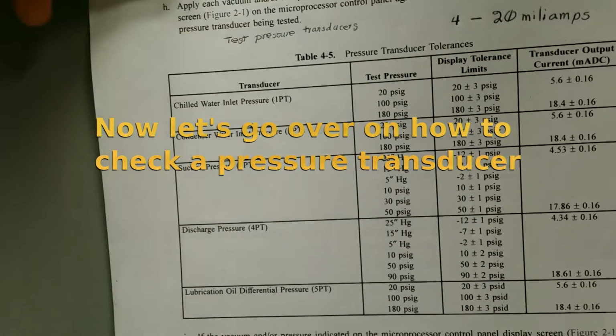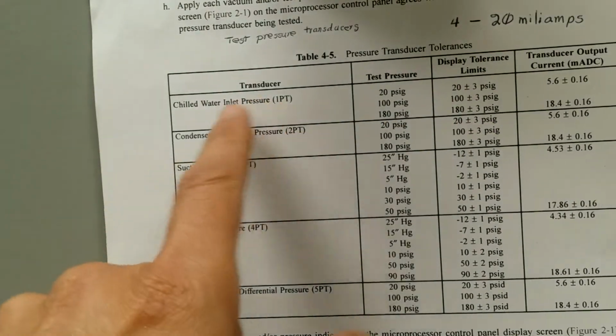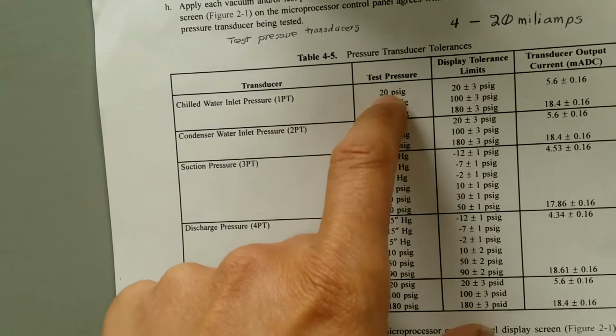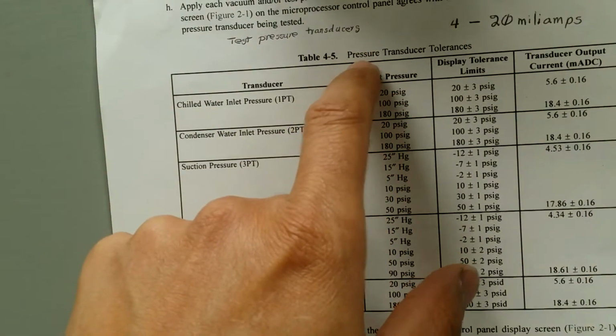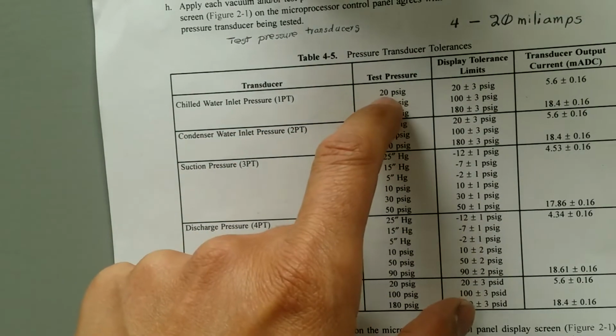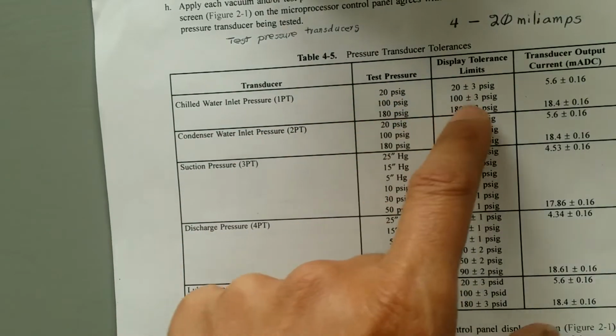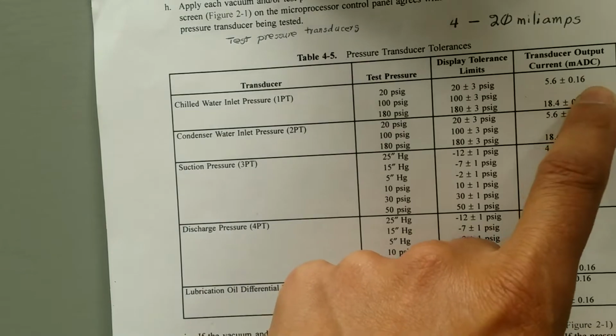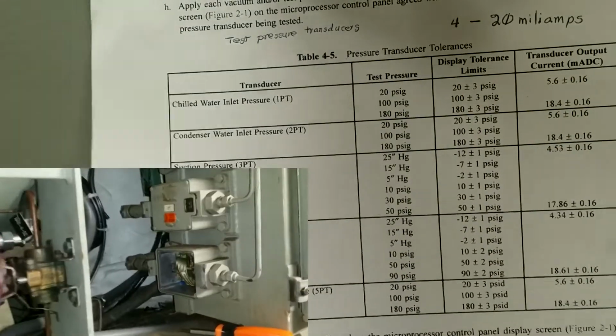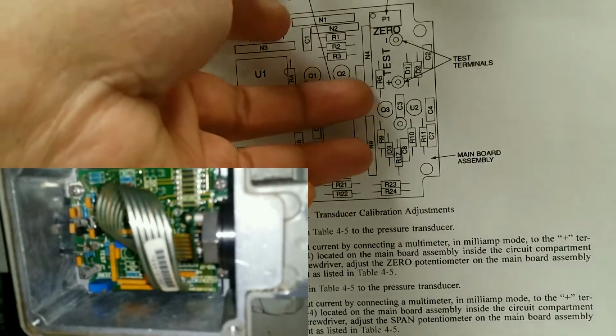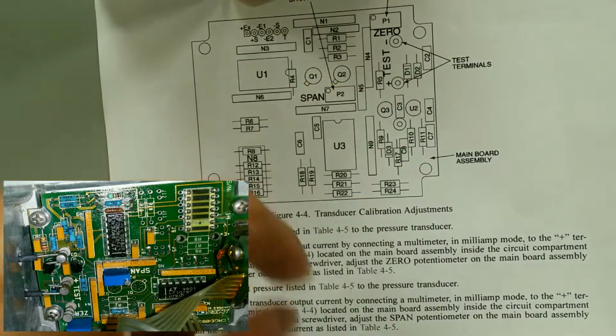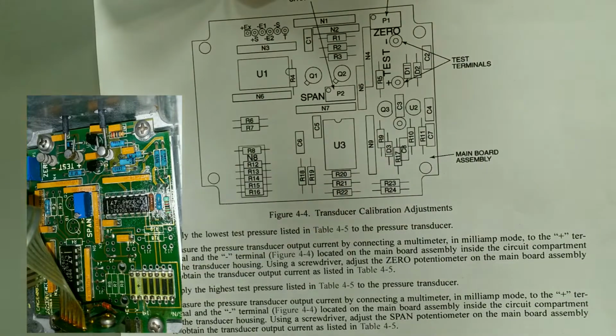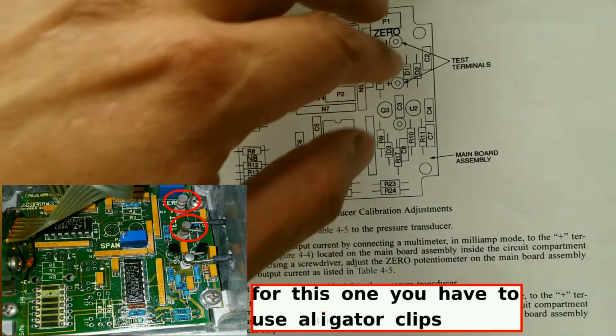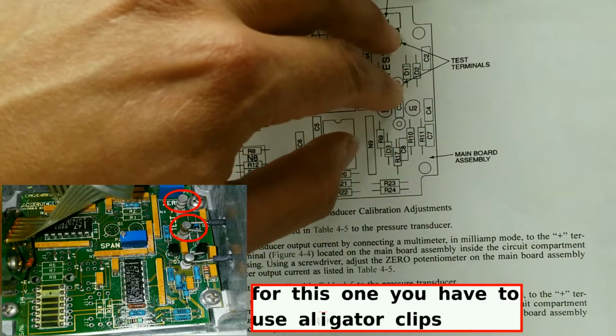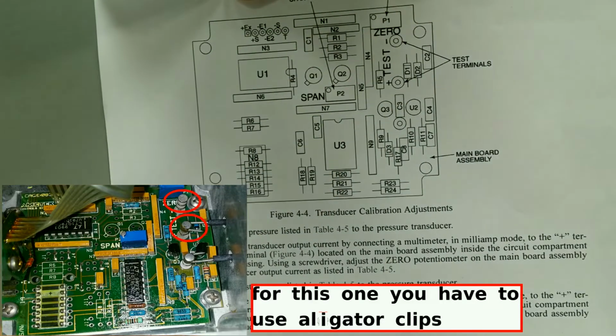To check if a pressure transducer is working, you have this chart over here, the pressure transducer tolerances, and based on whatever pressure it is, you should have a current going through it. You have to check the pressure transducer with power on, and it's a small voltage, only 28 volts. You go out there and stick your multimeter in. It has to be a true RMS multimeter, and you stick both leads in here, and you should get the 28 volts as the procedure tells you.